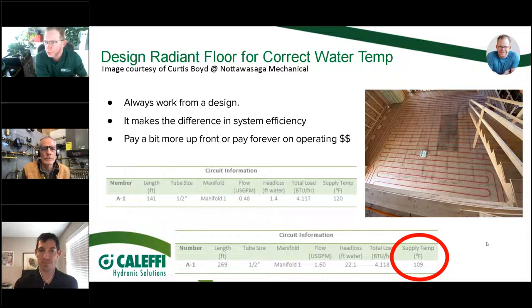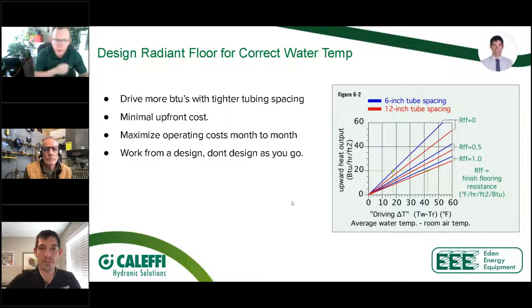Now, overall on COP, your COP just went through the roof. It doesn't matter whether it's a boiler, your boiler efficiency is going to improve. Everything gets better regardless. But what we did here was we just increased tubing. And the one thing that we all know is the least expensive part of the system is the plastic pipe, right? So for us to put in 6-inch versus 12-inch spacing, that's maybe $300 worth of pipe. But what does that mean every single month? If you just knocked $50, $60, $70 off their utility bill every single month for the life of that equipment, that's a big difference. We need to make sure that we're paying attention to that as we're going forward.